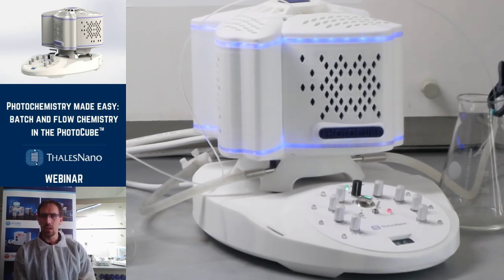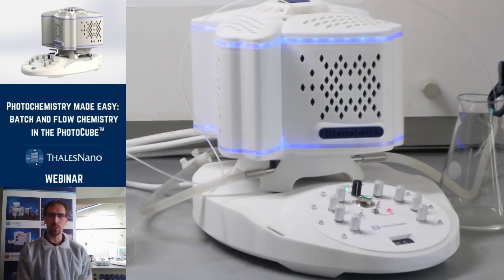Can you use the H-Cube Pro and the PhotoCube together, I assume? Yes, in principle you can use it. However, for the PhotoCube you need to use polymer tubing like FEP or PFA, and those will typically not be able to handle 100 bar pressure, so you would need to work at lower pressures.